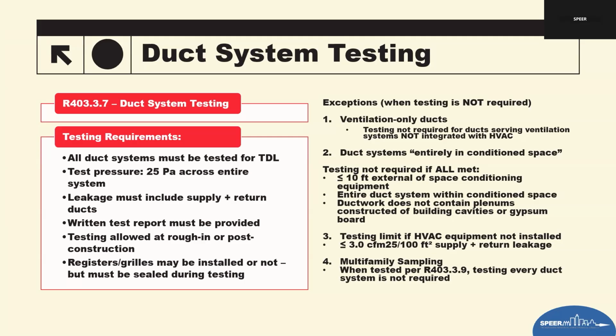And then also ensure that no building cavity plenums or gypsum board plenums are used. We're not using building cavities. If the equipment is not installed, we did this through COVID when there was a lot of equipment shortage, but when there's no equipment installed, your testing goes to a stricter limit of 3 CFM per 100 square feet of conditioned floor area. We'll see that in the table in just a second.